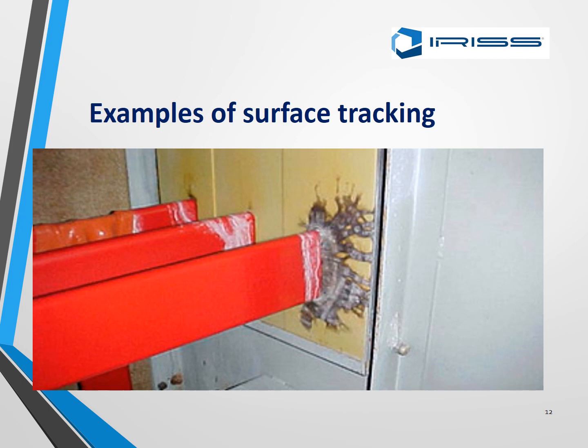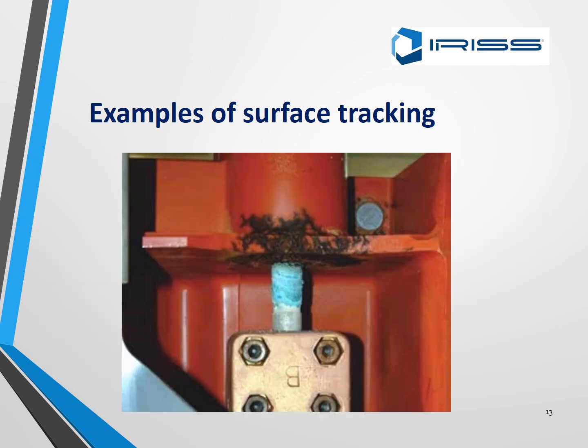Another example of tracking — this is a bit more severe. Around the busbars you can see the white residue, which is the first part of the corona. This has been left to continue and that is why the tracking has got worse. In this next example the tracking is getting darker because the white residue powder has now started to oxidize, changing colour.